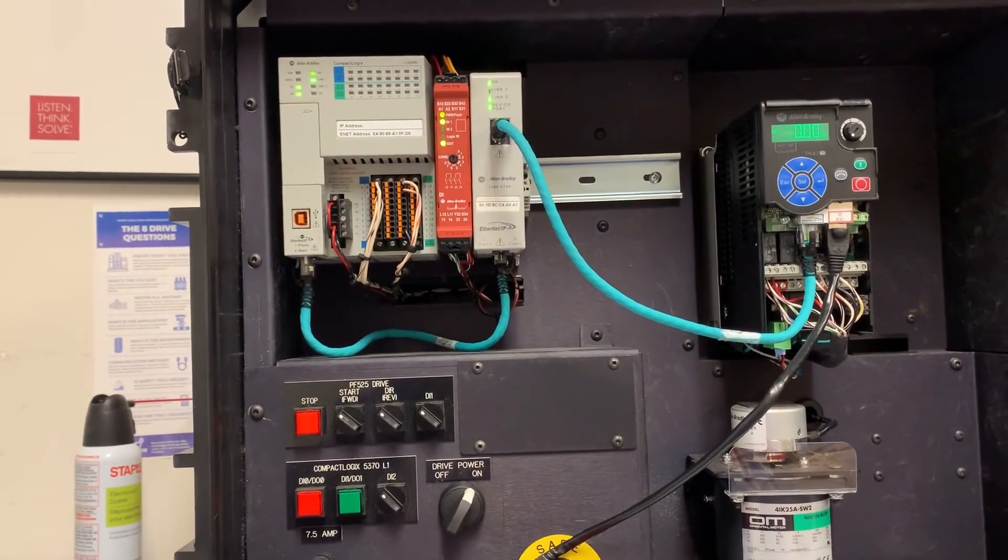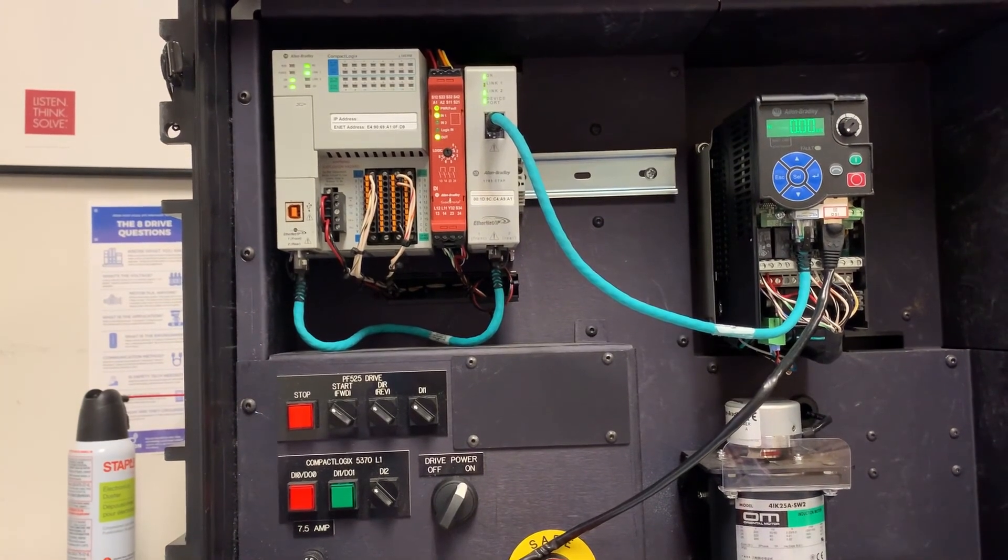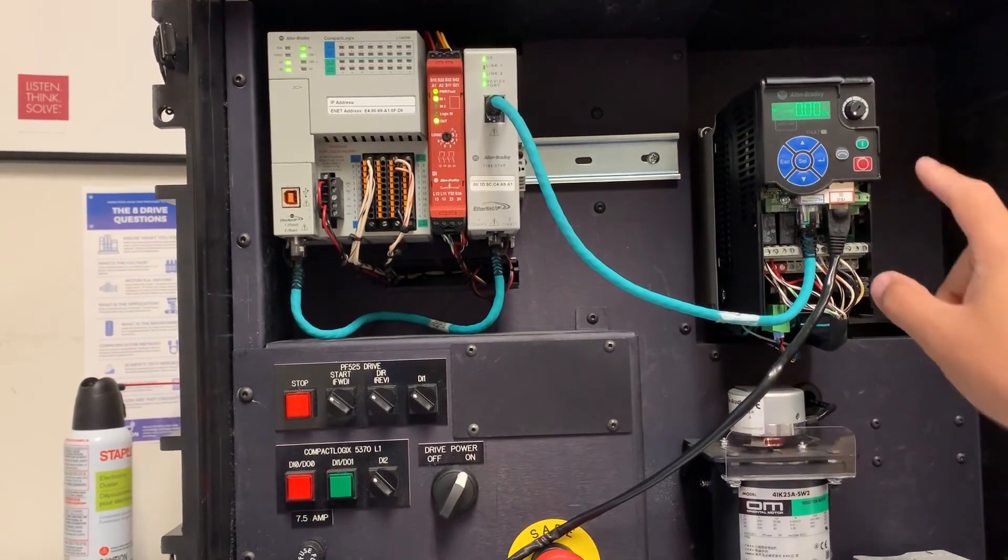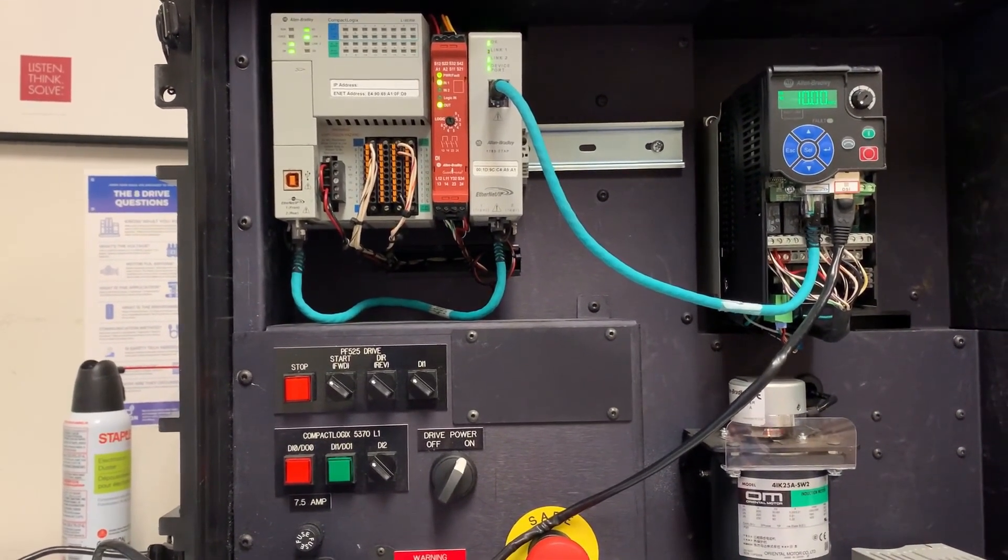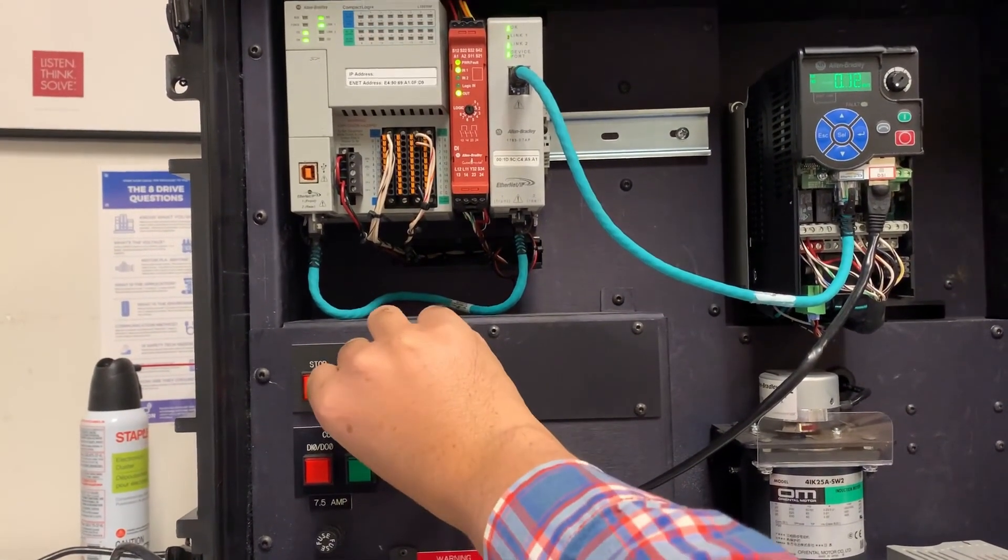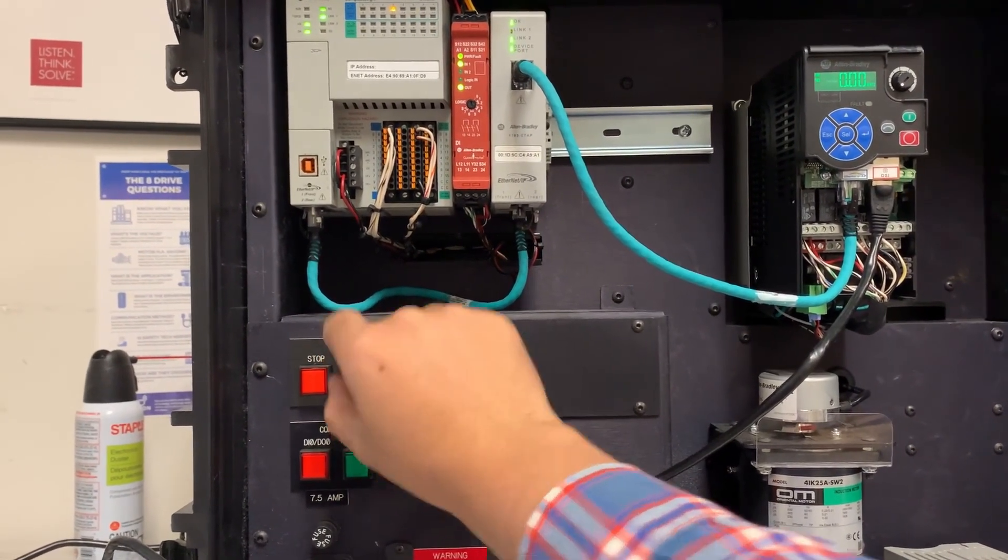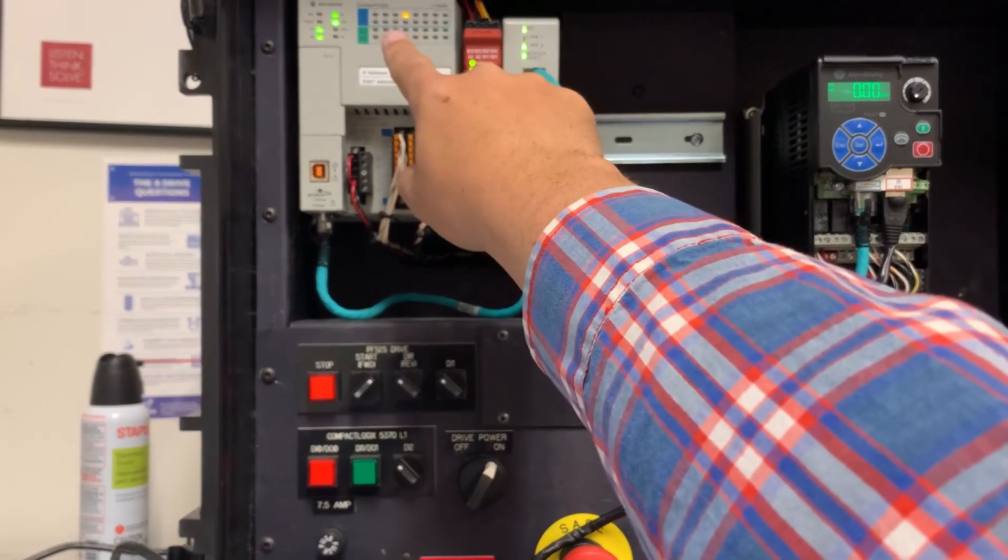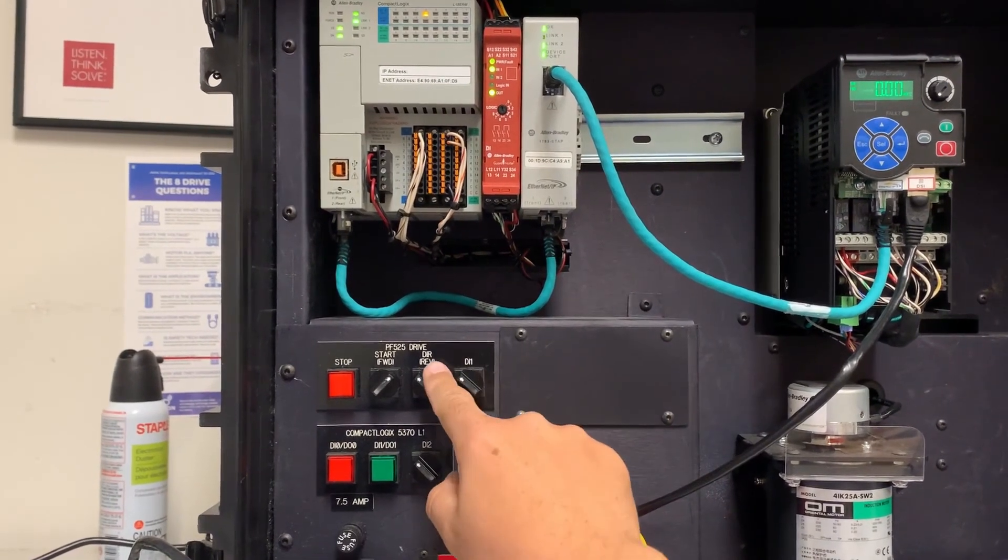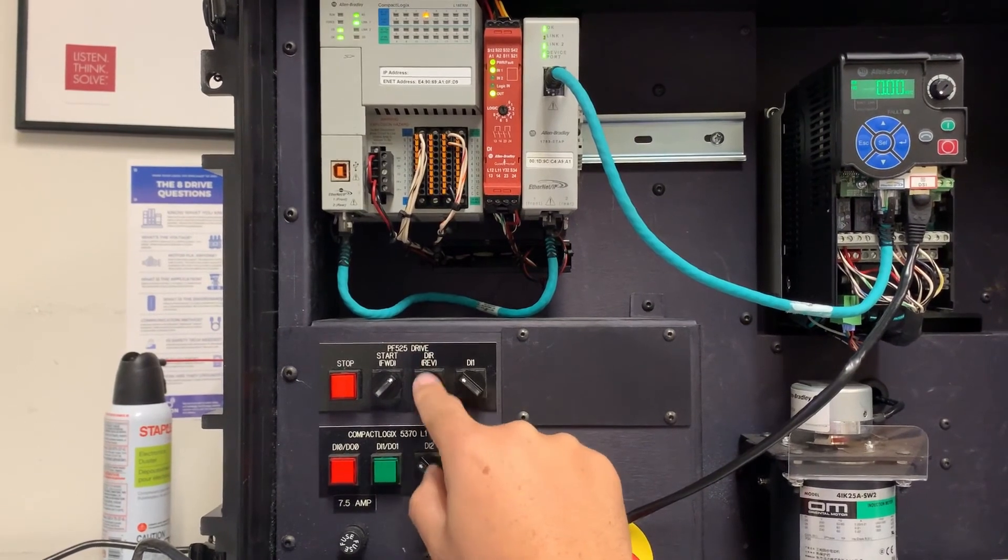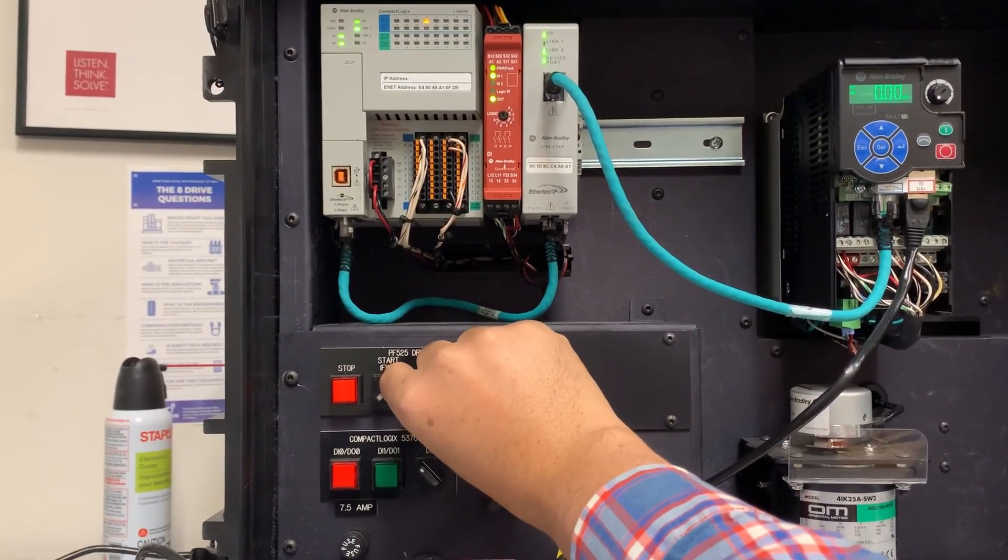All right, everybody. And to test out our setup, I have in front of us a PowerFlex 525 demo kit with the positioning program installed. I'm going to begin by pressing the start key on the keypad, which is our start source. And you can see the drive is automatically moving into position. I'm now going to engage this switch, which represents the photo eye under the dispenser, indicating that the drive is positioned. You notice the drive immediately stopped and that a signal has been sent to the controller to allow it to know that it can begin the dispense action. I'm now going to engage this switch to represent the dispense action being completed by the controller, which is an input to the drive, which will tell it it can move back to position zero.